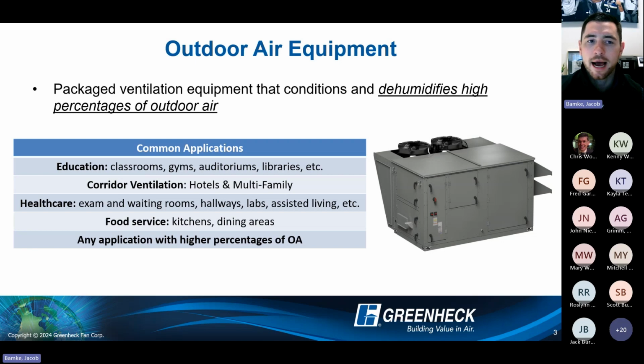And when we talk about high percentages of outdoor air, we're really talking about anything above 25% outdoor air. Not saying that these units can't operate down to 0% outdoor air, but from a size, performance standpoint and the construction and components used, they are really geared towards designing around that 25% to 100% outside air.